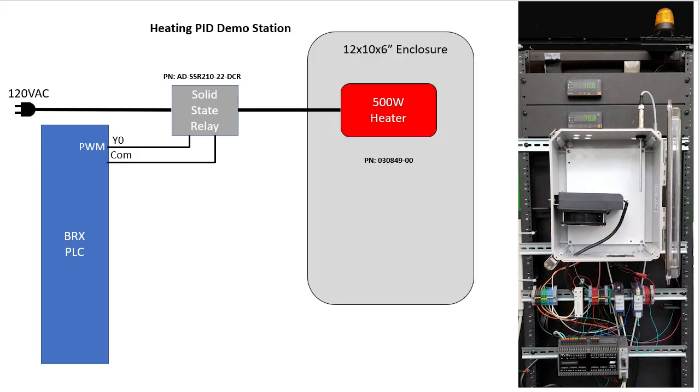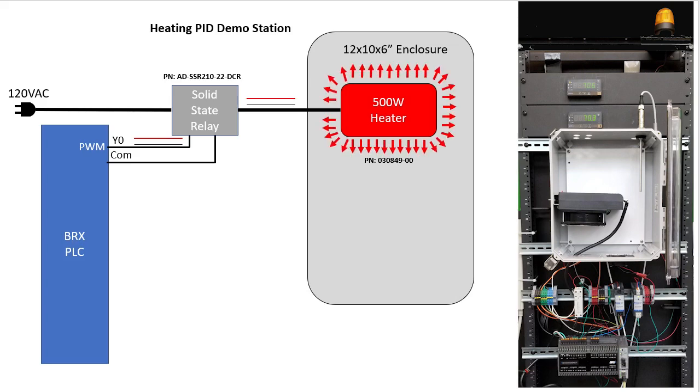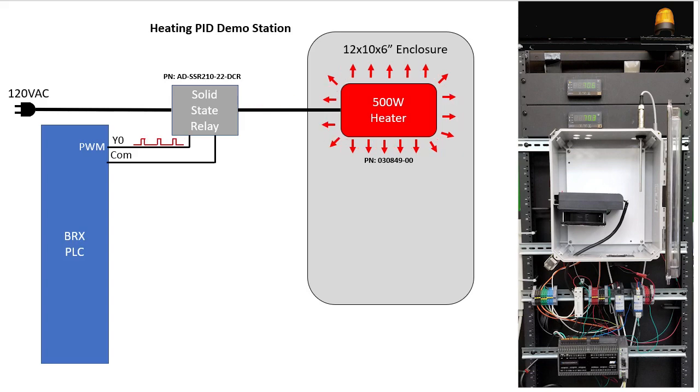If the PWM signal is on all the time, the heater is on all the time and we get all 500 watts. If the PWM output is set to a 50% duty cycle, then the heater is only on half the time and we get half the heat. A 25% duty cycle gives us 25% of the heat, etc. We'll see how easy that is to set up in a Do More PLC in just a minute.